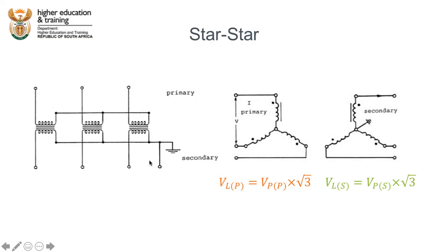This is what the star configuration would look like diagrammatically. On the primary side, all three coils are connected in a star formation — every coil connected together at one central point. The same thing happens on the secondary side: the end of every coil is connected to a single point. Because it is in a star configuration, we have the ability to connect a neutral to this single star connection point, and we are therefore also able to connect this to ground.